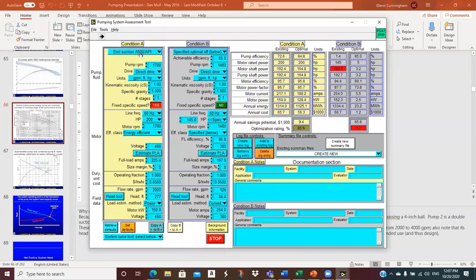We'll just stay with this one. So then we have information on the pump, the fluid, the motor, how much time it operates, and the cost of electricity, and then field data, hopefully things that you've gone out and measured in the field. So those are all of the inputs. Pump RPM could be a rated RPM, or it could be a measured RPM if you actually measure it. It's probably better to measure it. And you just put in whatever number that you have here.